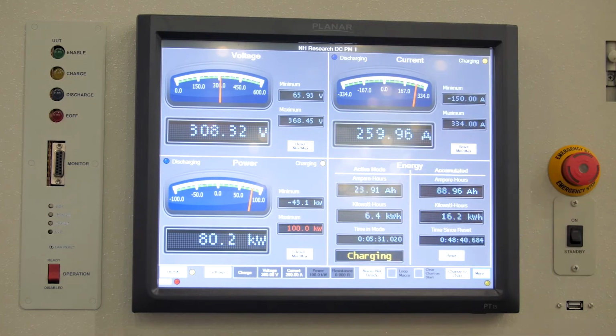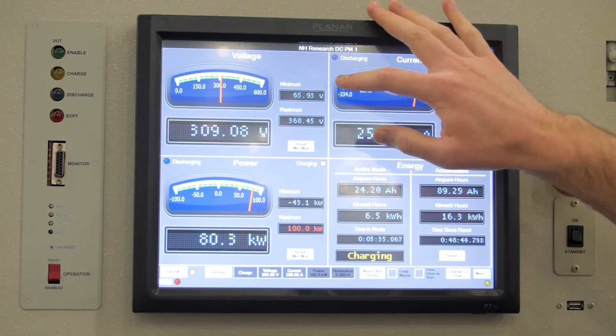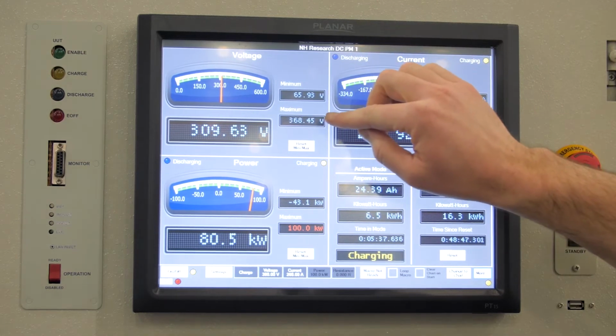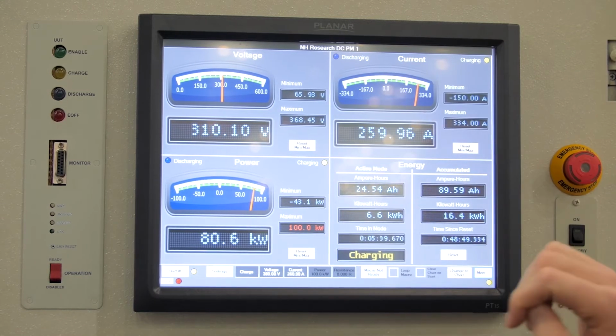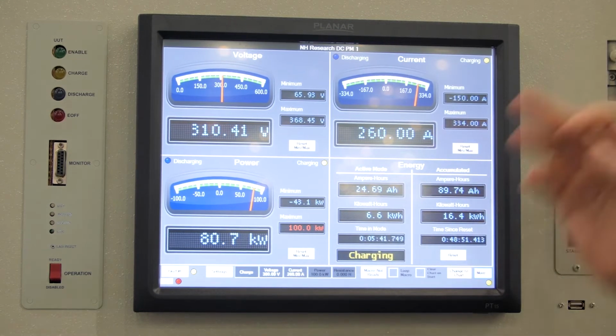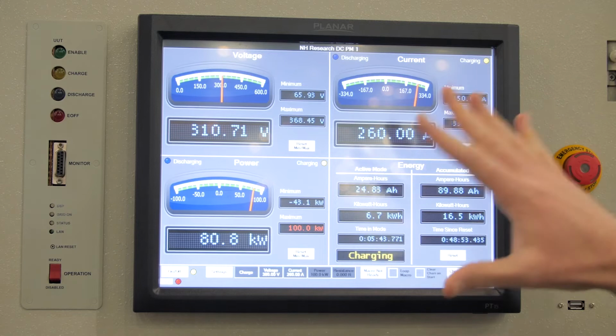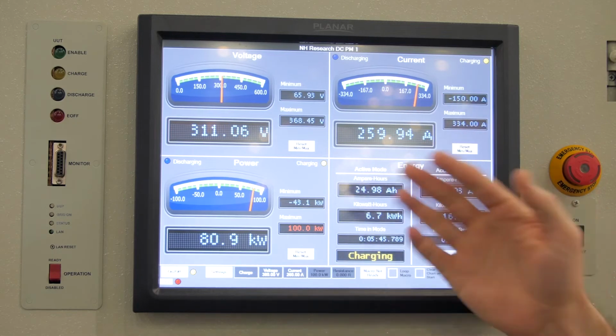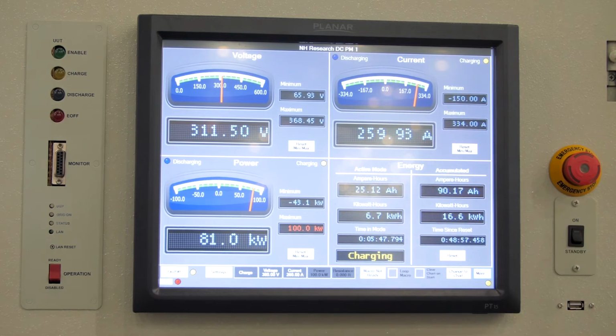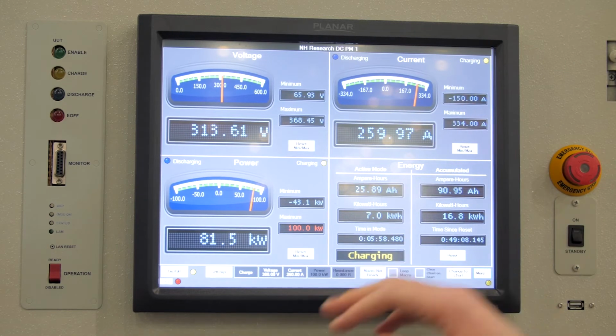So this is in the set time test that you've been working. It tells you exactly how low you've gone and the absolute maximum, how high you've gone as well. Of course, we're monitoring this repeatedly. Off the touch panel, we can do measurements within half-second intervals. Certainly with the software-driven LabVIEW drivers and things like that, we have much more measurement capability, but the touch panel itself can do half-second intervals for measurement.